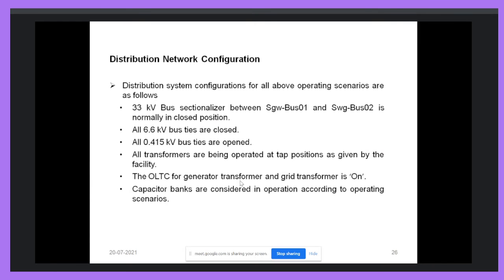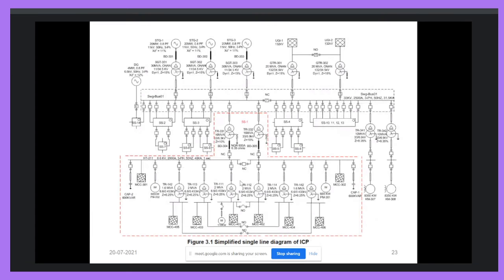We have seen the single line diagram. Here we can see the utility power supply is available at 33 kV. We have integrated the generator and utility system at the 33 kV voltage level, and the power is distributed at 33 kV, further stepped down to 6.6 kV and distributed, and the loads are connected at different voltage levels. This is the actual power distribution system of Bina refinery, and they have SCADA based load shedding and under frequency relay based load shedding. They do not have artificial intelligence based load shedding.